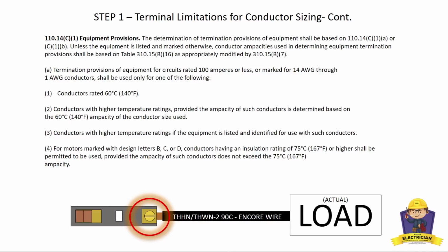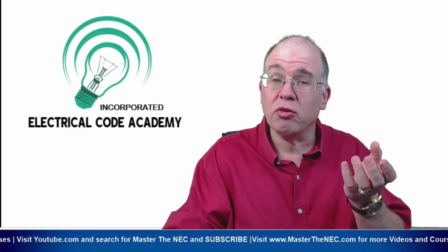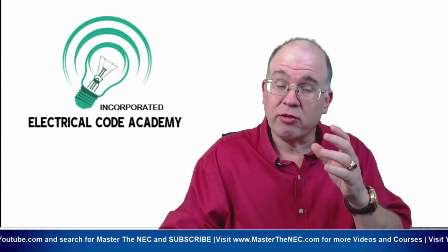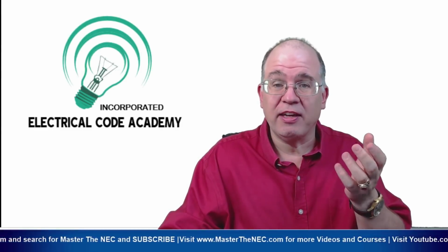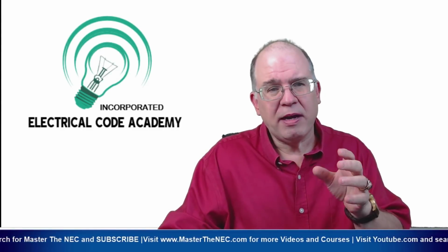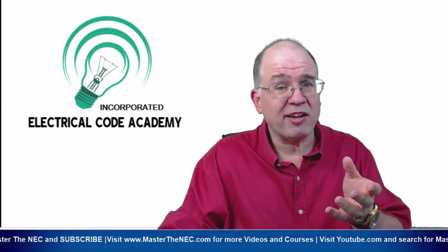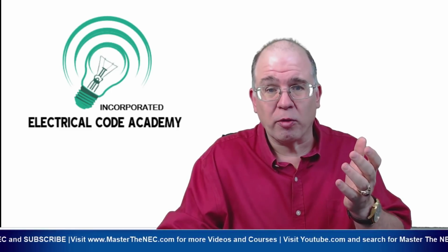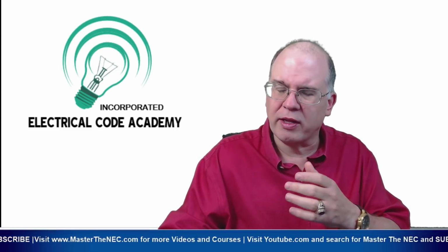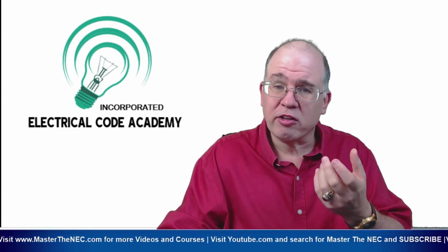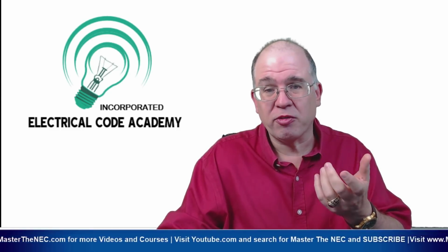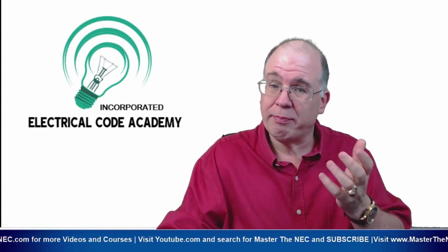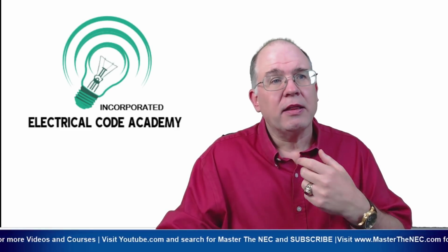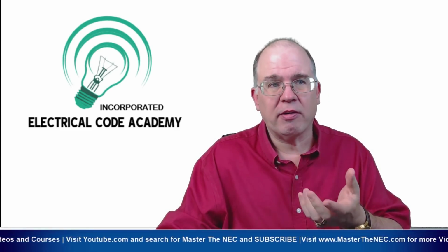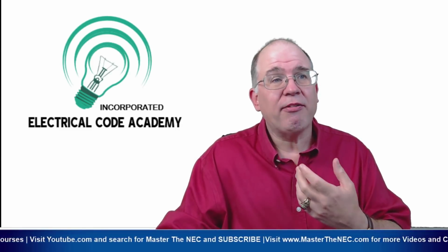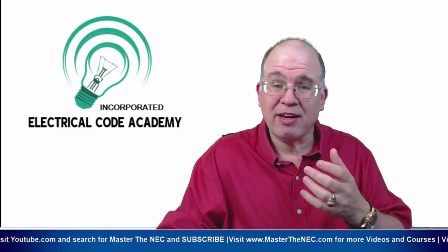So what we're saying here is that I can use the actual insulation value as, say, 90°C of a THHN. But because of its 14-to-1 conductors and nothing else is marked, or maybe it's an older piece of equipment I'm rewiring and there's no markings on it, but I know that I'm using a conductor that's 14-to-1 and the terminals maybe state that, or it's a 100 amperes or less application, then I'm going to pull an ampacity from the 60-degree column.